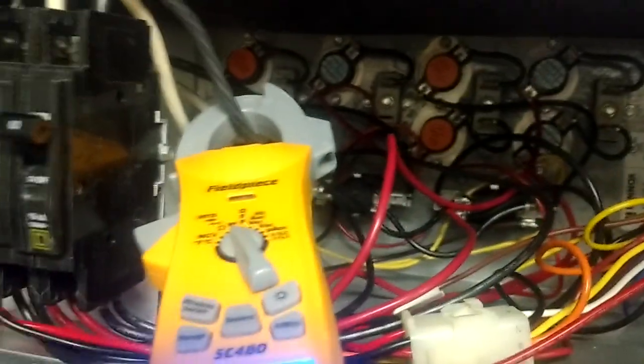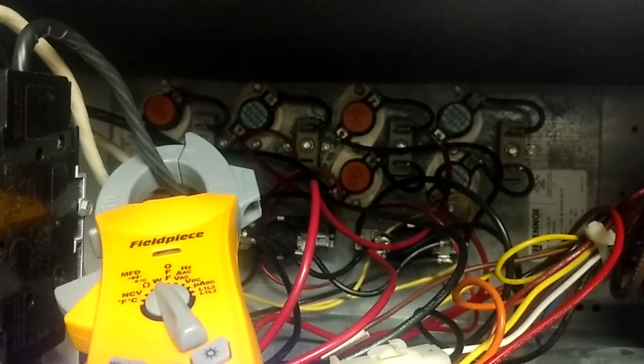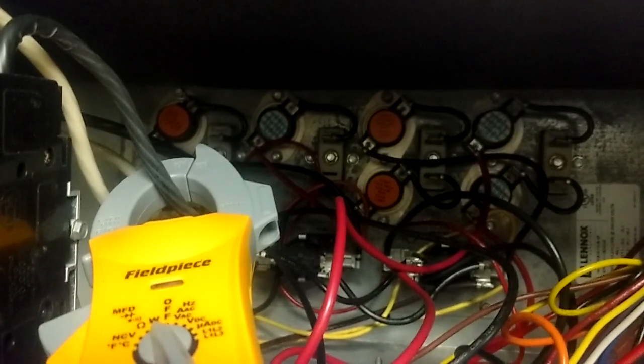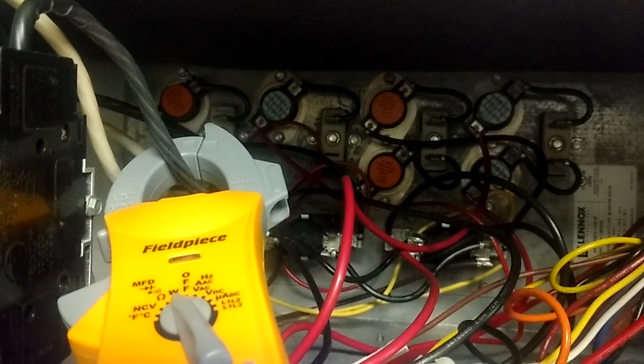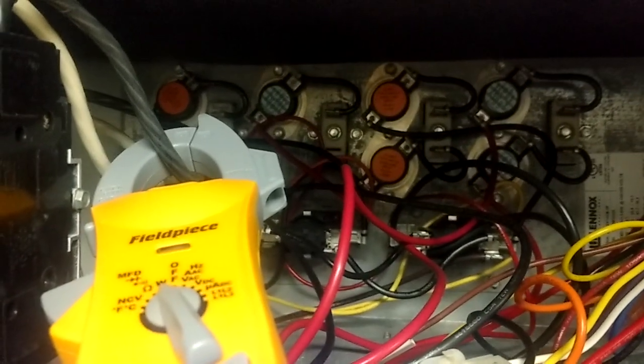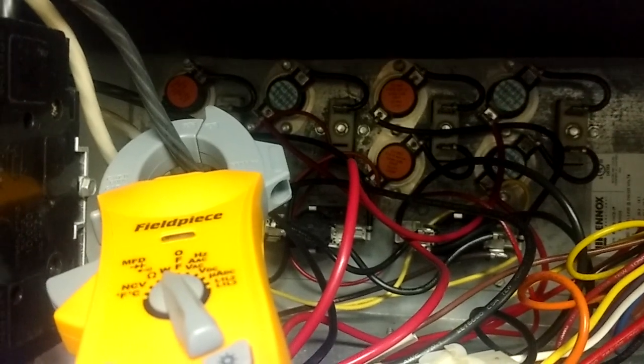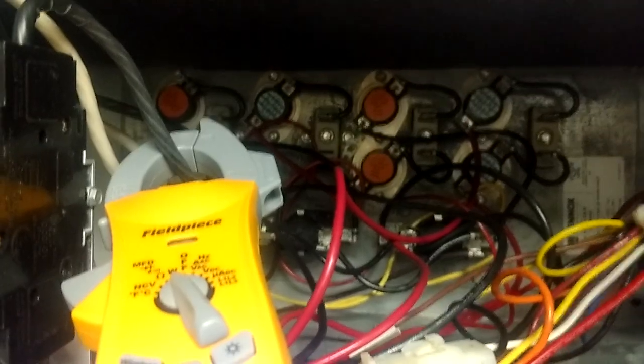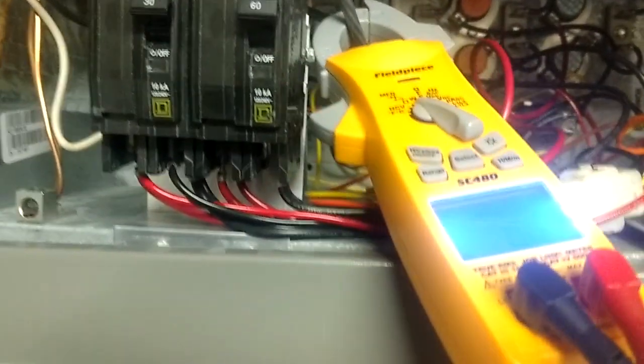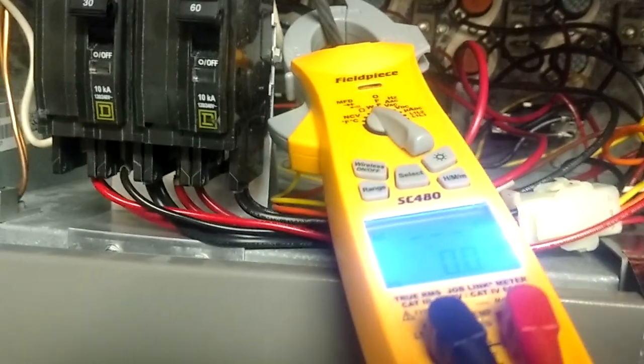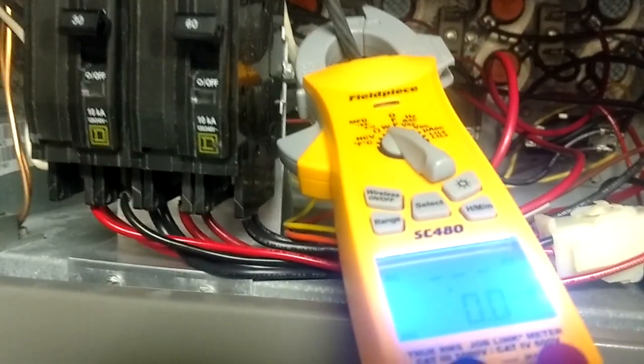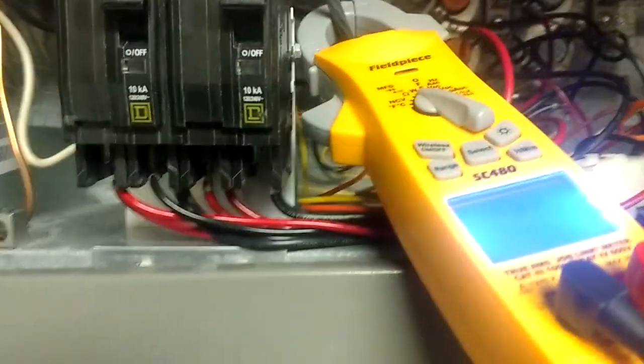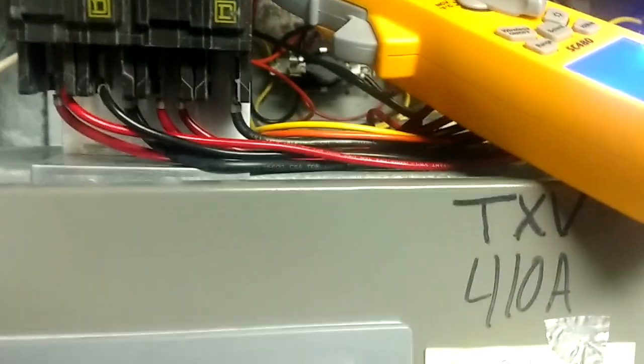If your power factor is lower, then that means that the unit's not using all the power you're putting in there. And so far, playing around with this setting, I have found a couple of outdoor units that are running like a 0.53 or a 0.75. And I'm not exactly sure what's going on there because the capacitor was fully charged. And I know Jim Bergman was talking to Zach about that one time, and he said that the capacitor on the outdoor unit is trying to get that power factor as close to one as it can, and that's why the capacitor has to be properly sized, and you should never change the size of a capacitor. So that kind of makes sense, but then it didn't really make any sense why I didn't have anywhere close to a power factor of one with a fully charged capacitor.